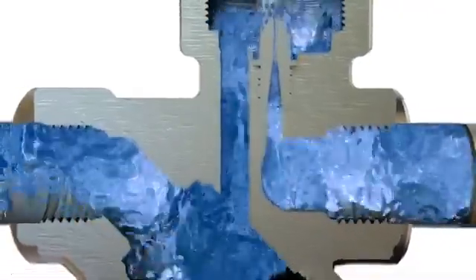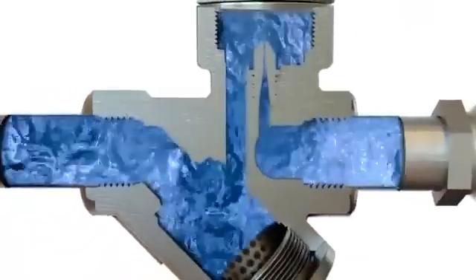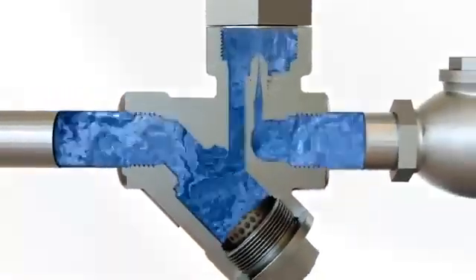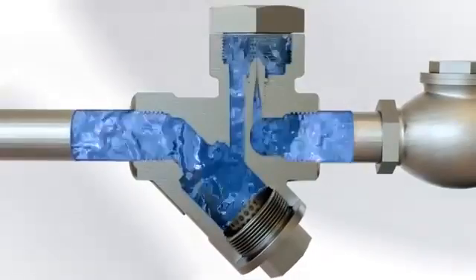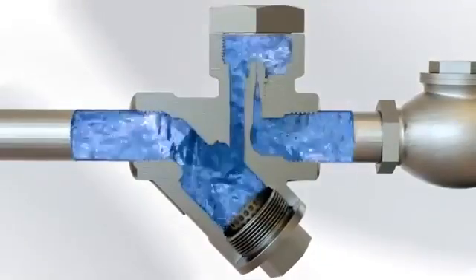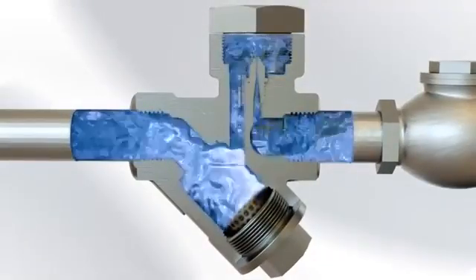This cold water exits freely at 2 to 3 times faster than hot pressurized condensate can at running load. This absence of flash steam on startup is why Delta Venturi Orifice Steam Traps are suitable for startup loads.